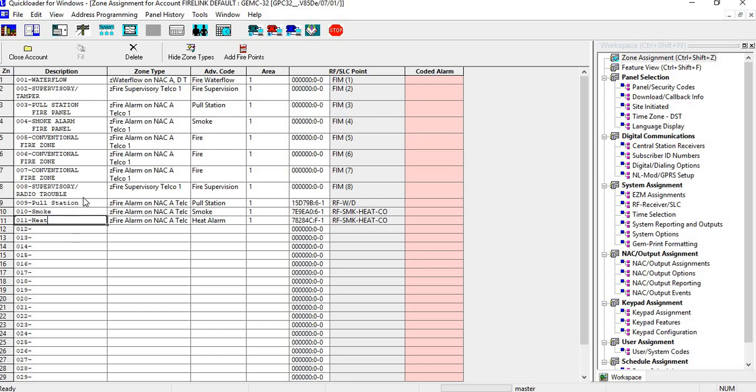Just a word of warning with the pull stations: you're going to use a WD2, and you're going to need to look in the instructions because they could be used for burg or fire. If you hook it up as a fire, you'll only be able to use 0.1, and you have to move a jumper and you have to use a resistor.